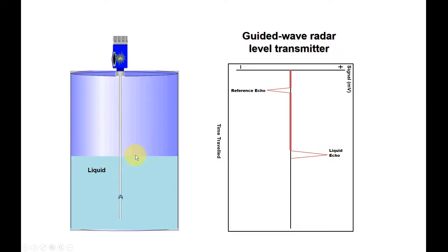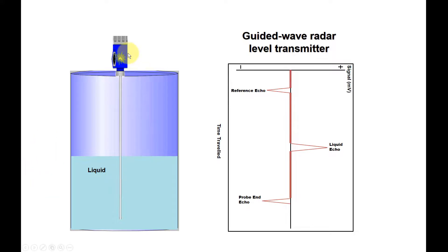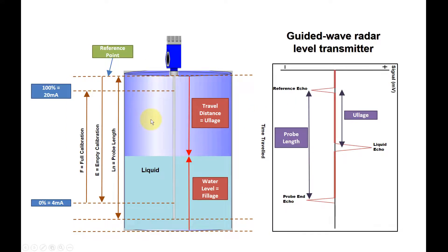Then this remaining signal will continue to travel all the way back to the level transmitter and be detected by the level transmitter electronic board. You can see the echo is formed here — this is called the probe end echo. This is the measurement for the level transmitter.